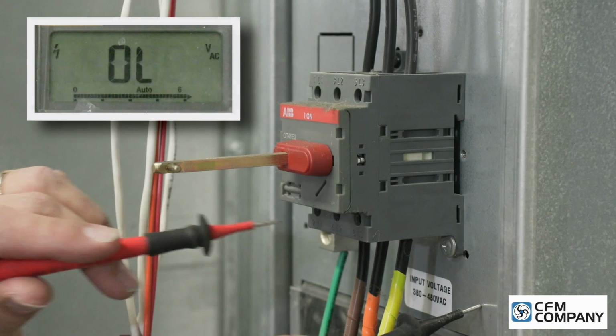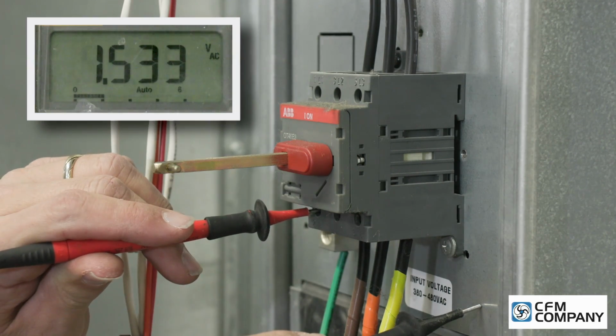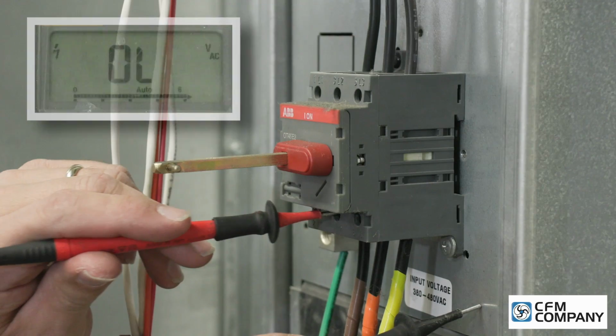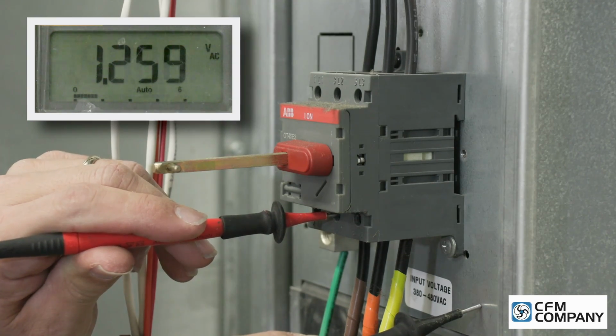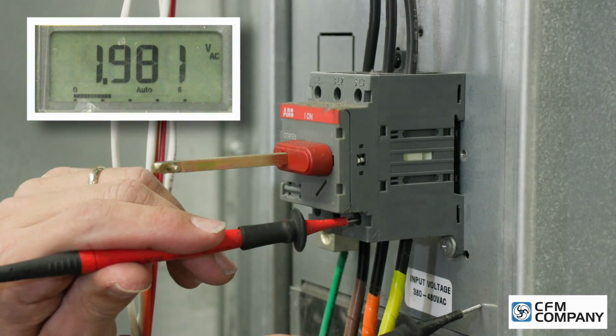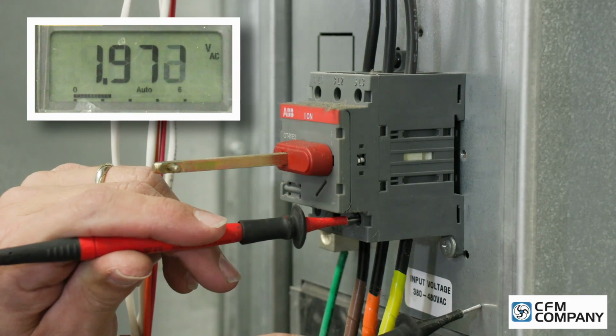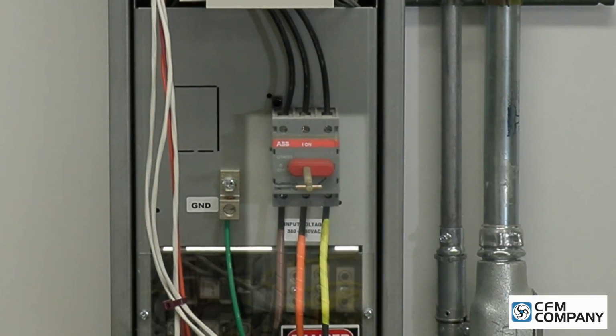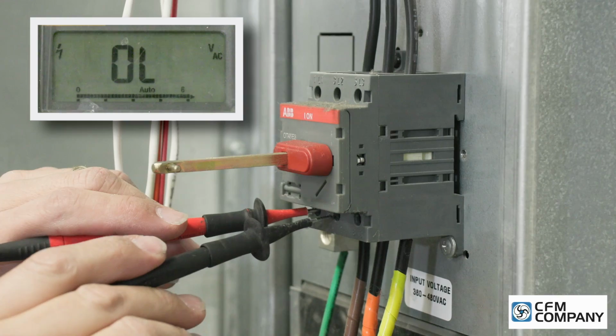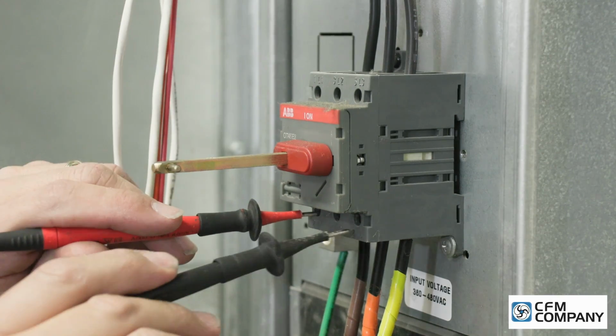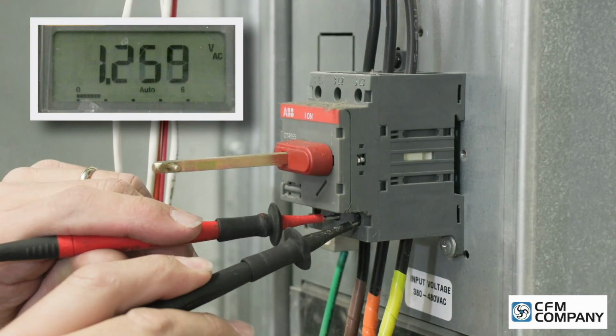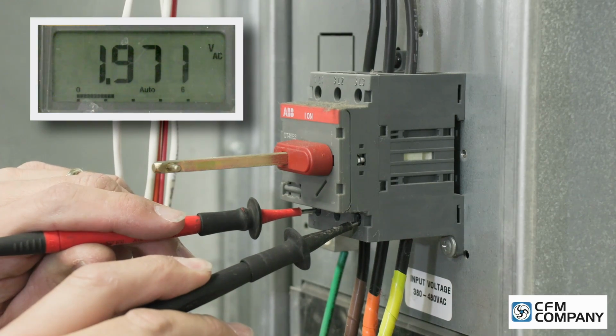Check the line side voltage, line A to ground, line B to ground, line C to ground. These readings should read near 0 volts AC. Check the line side voltage, phase A to phase B, phase B to phase C, phase C to phase A. These readings should read near 0 volts AC.